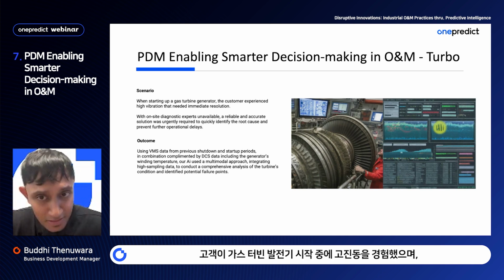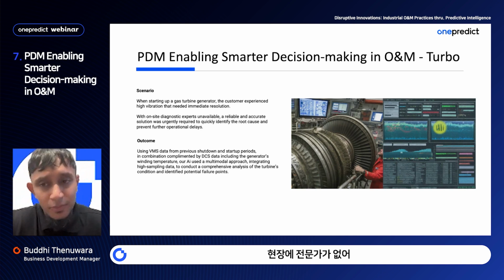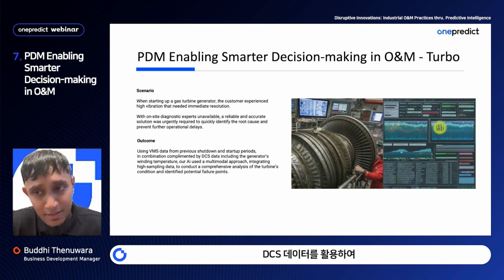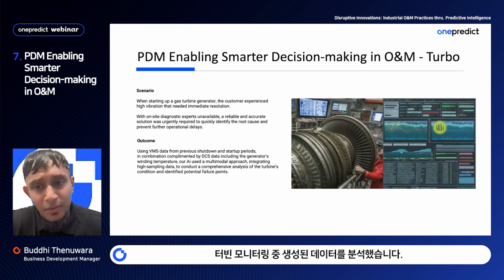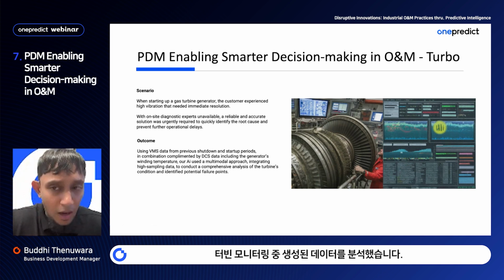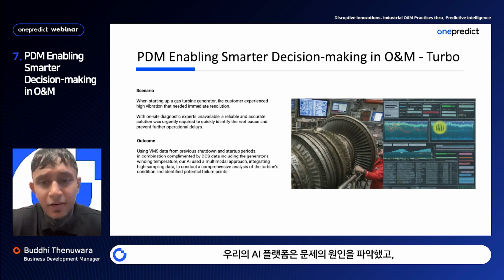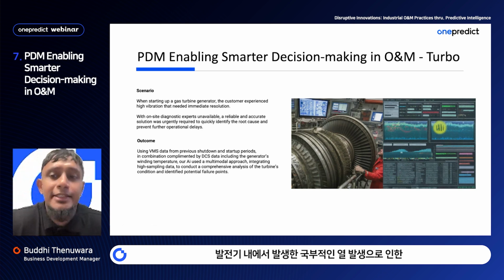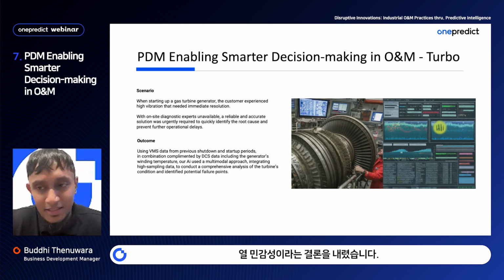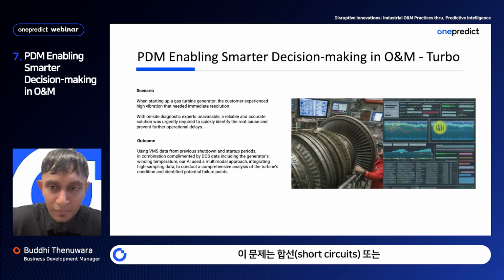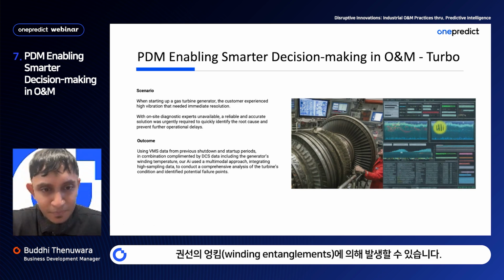A customer experienced high vibration during a startup of a gas turbine generator. With no on-site experts available, they needed an immediate solution. Using VMS data from previous shutdowns and DCS data monitoring the generator's winding temperature, our AI platform identified the root cause, which was thermal sensitivity due to localized heat generation in the generator. This is potentially caused by short circuits or winding entanglements.